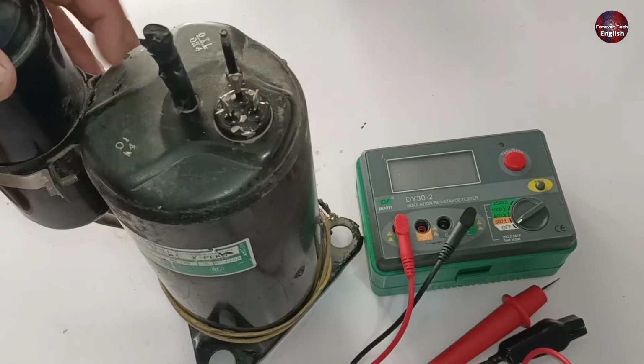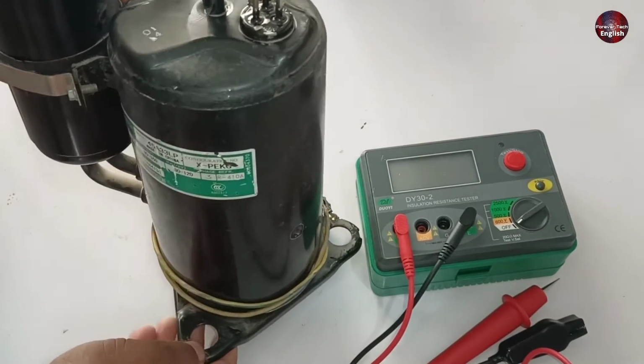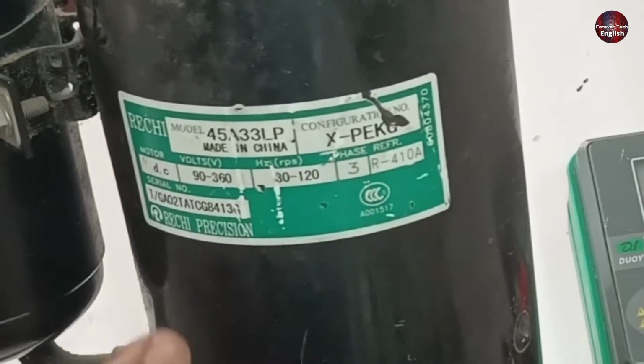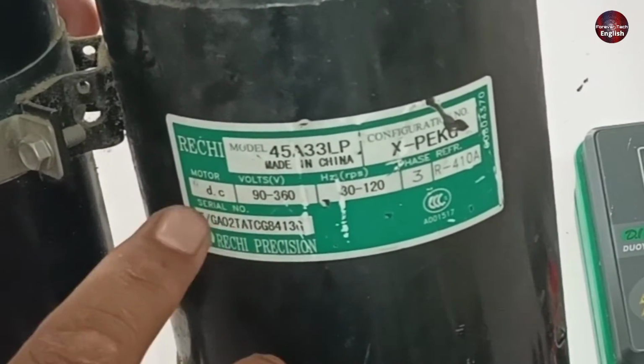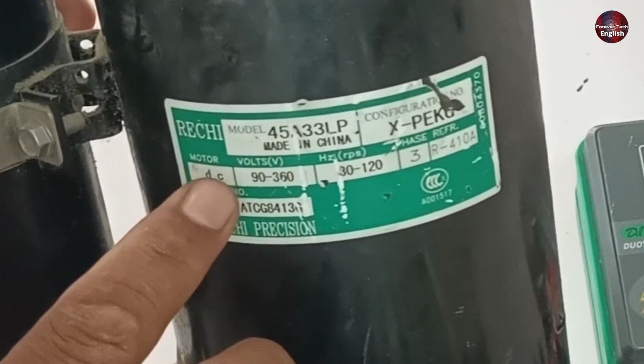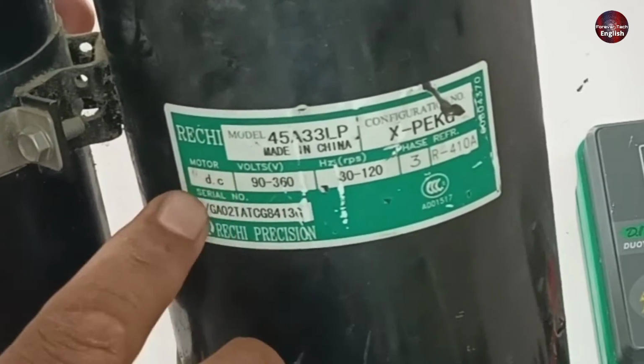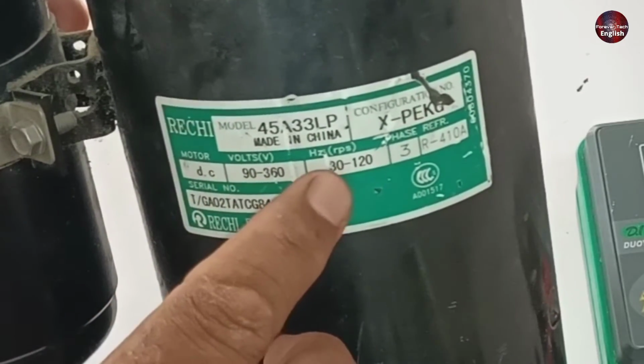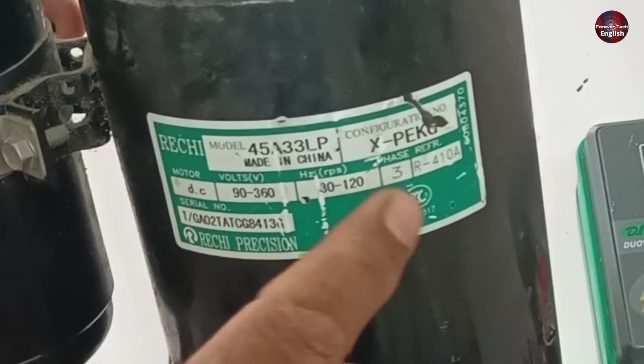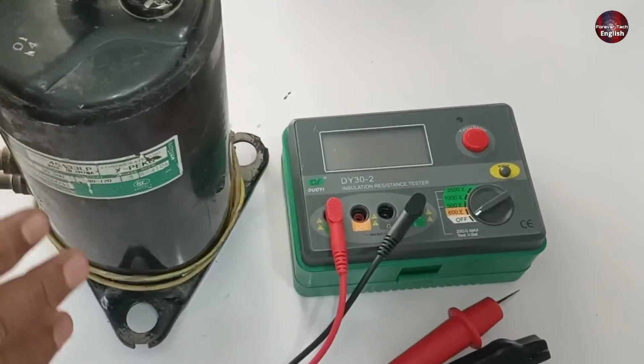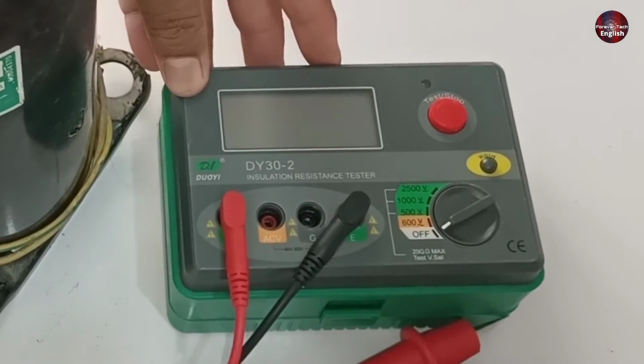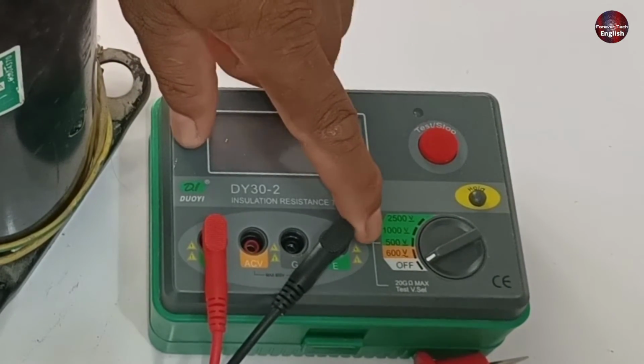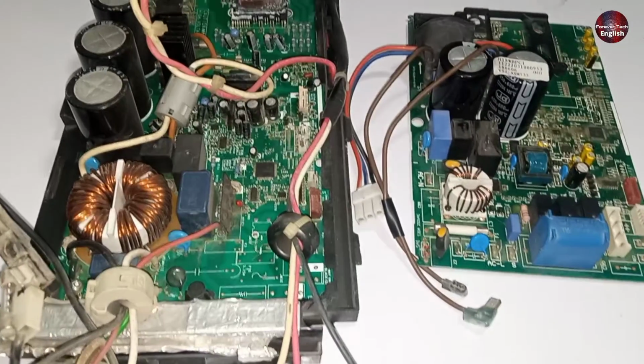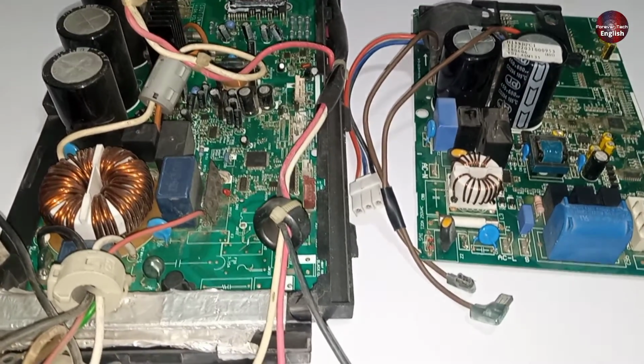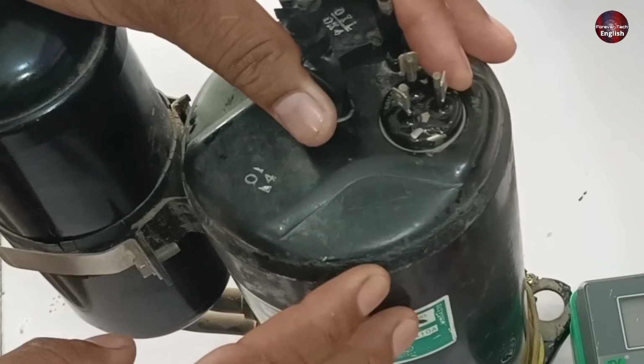Now a thing to understand is whether you check an AC compressor or a DC compressor. The operating voltage range is written on its specification sticker. This compressor operates from 90 to 360 DC volts. And the frequency range is 30 to 120 Hz. And whenever you are testing an HVAC compressor, also check this. And the insulation tester should always be kept between 500 to 1000 volts. Because when this DC compressor operates, the control board passes a maximum of 380 volts to these compressors.